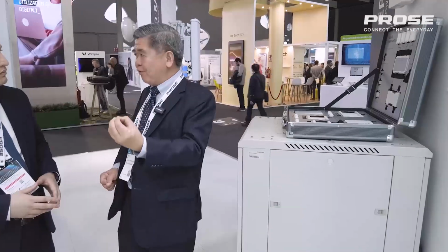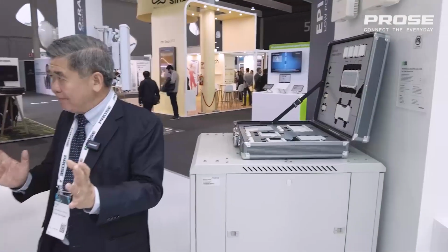With 4x4 MIMO, if I use a high power solution with a passive DAS, I need to run 4 feeder cables over large distances. That makes the installation cost very high and also very prone to PIM, passive intermodulation issues. But with the active DAS, it's simply laying a hybrid cable with 4 fibers with the power cables, and you can deliver 4x4 MIMO with unlimited bandwidth.